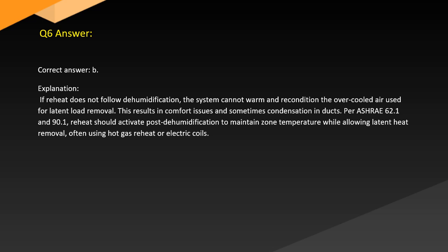Answer. Correct answer: B. Explanation. If reheat does not follow dehumidification, the system cannot warm and recondition the overcooled air used for latent load removal. This results in comfort issues and sometimes condensation in ducts. Per ASHRAE 62.1 and 90.1, reheat should activate post-dehumidification to maintain zone temperature while allowing latent heat removal, often using hot gas reheat or electric coils.